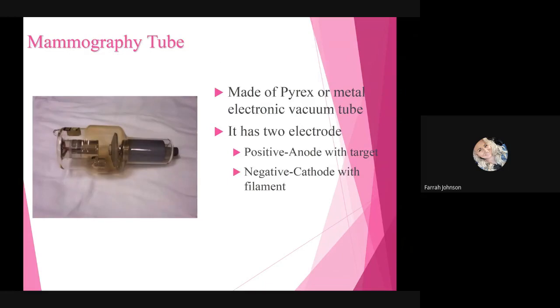So now we're going to get into your mammography tube. So this is an example of what your mammography tube looks like. It's typically made of Pyrex or metal, and it also has an electronic vacuum. It has 2 electrodes. The positive end of your mammography tube is going to be your anode with the target, and the negative end is going to be your cathode, which contains your filament.